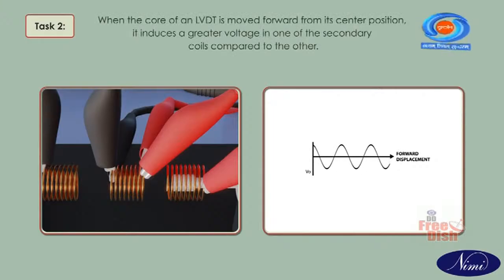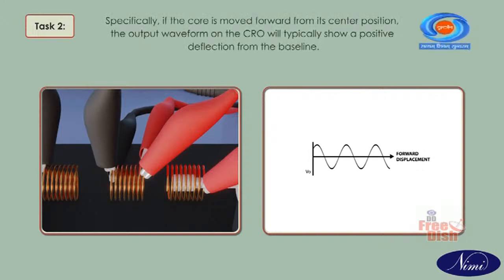When the core of an LVDT is moved forward from its center position, it induces greater voltage in one of the secondary coils compared to the other. Specifically, if the core is moved forward from its center position, the output waveform on the CRO will typically show a positive deflection from the baseline.